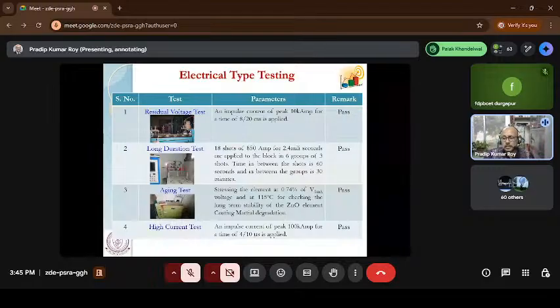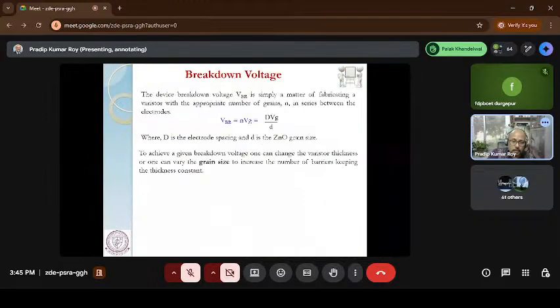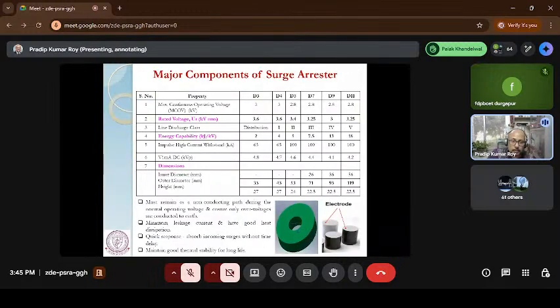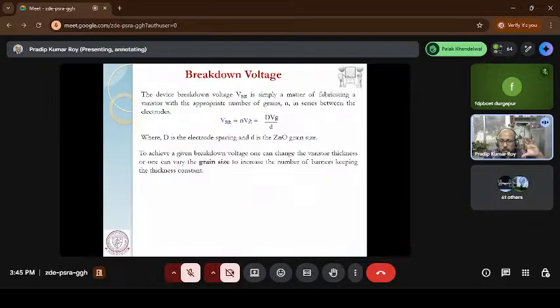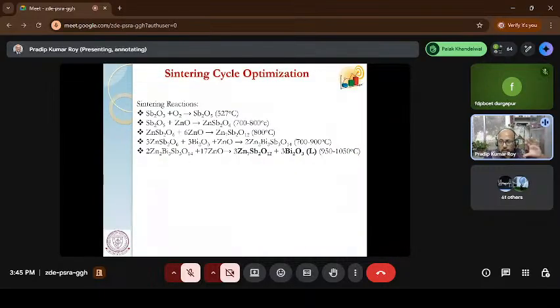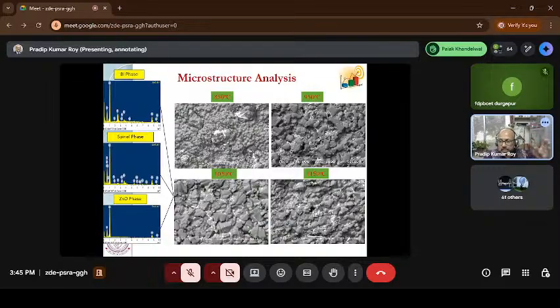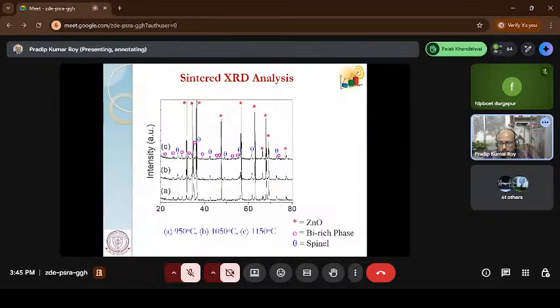And for the long duration test, normally what energy handling capability should the block have? If you remember the slide, for this D3 block, the energy handling capability is 2. So if I take 30 blocks together, the energy handling capability is 60 kilojoule per kilovolt. Based on that, my surge voltage should not be more than 60. Otherwise, it will break that surge arrestor.